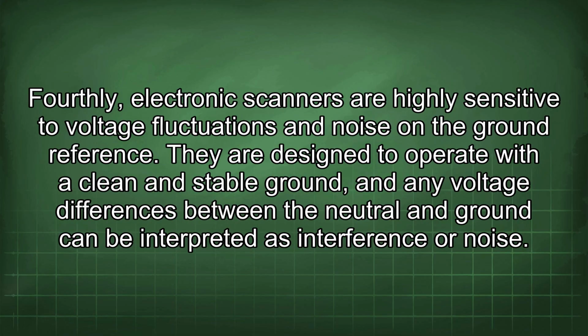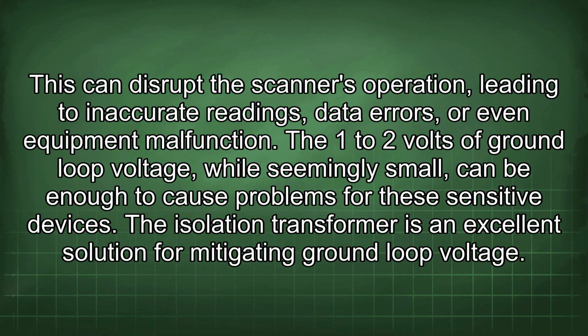Fourthly, electronic scanners are highly sensitive to voltage fluctuations and noise on the ground reference. They are designed to operate with a clean and stable ground, and any voltage differences between the neutral and ground can be interpreted as interference or noise. This can disrupt the scanner's operation, leading to inaccurate readings, data errors, or even equipment malfunction. The 1 to 2 volts of ground loop voltage, while seemingly small, can be enough to cause problems for these sensitive devices.